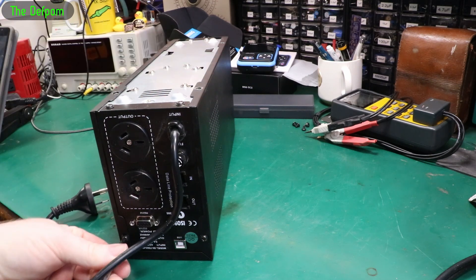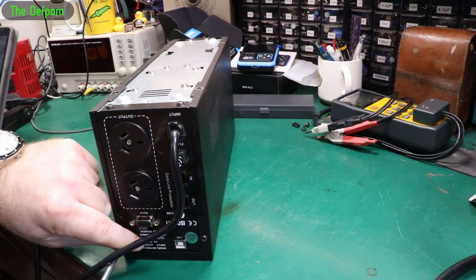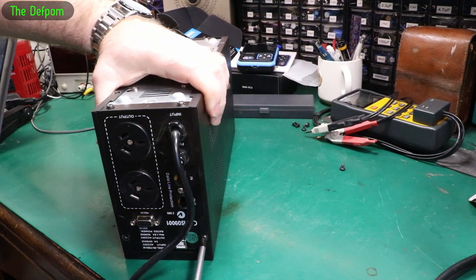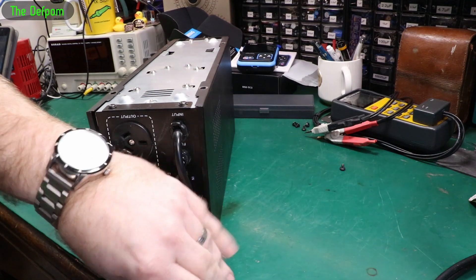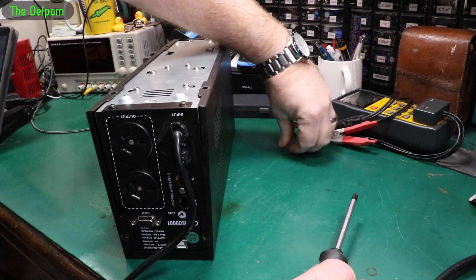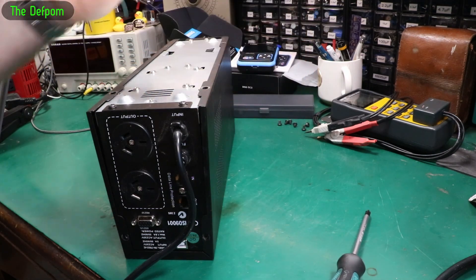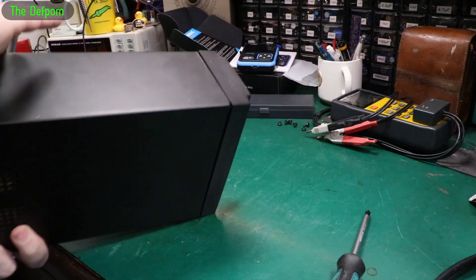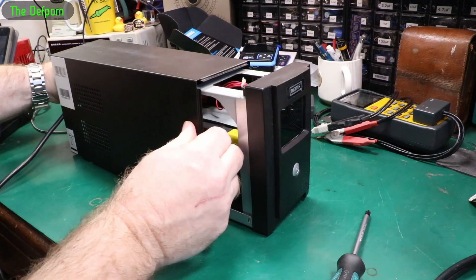This is a line interactive UPS — it supports line voltage, so if you've got a brownout where the voltage drops on your mains AC coming in, it will help support it and replace it. We've had lots of issues recently with that, so I think this was working quite hard, switching in and out a lot, and that's why the battery's suddenly just gone — it's getting old and it's had enough. I think the battery's had it.